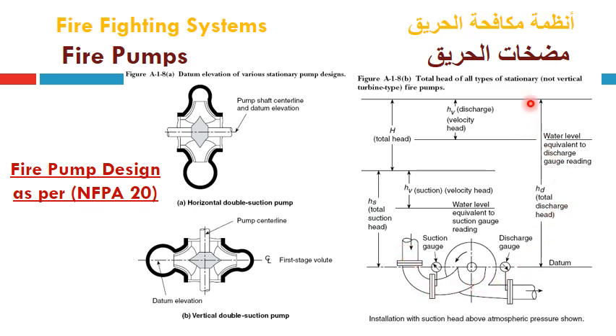The same also the additional term of velocity head to be added to the static term of the static discharge head to get the total discharge head, which is equal to the H velocity of the discharge line plus the H static discharge. So then we can evaluate the total head required for this pumping system from this level up to this level.